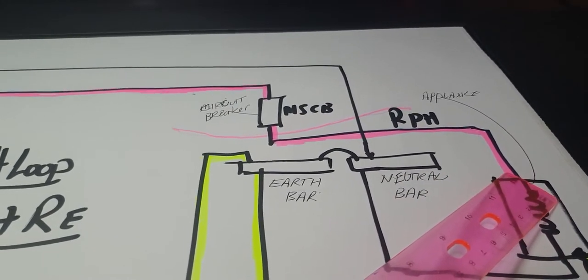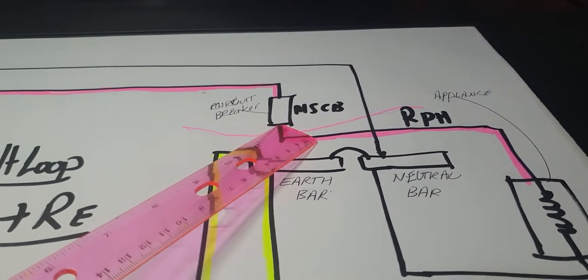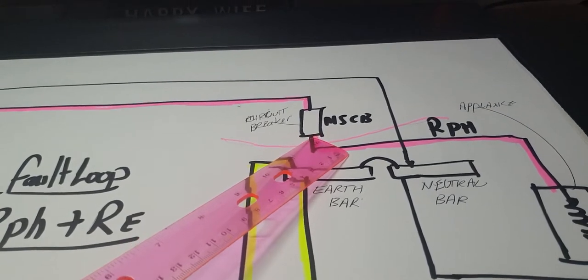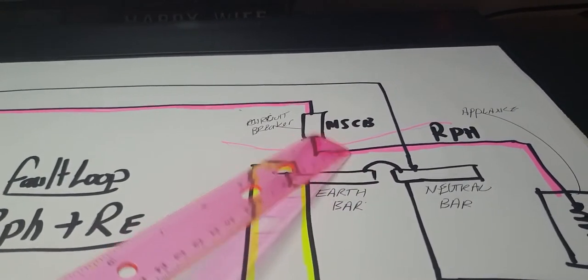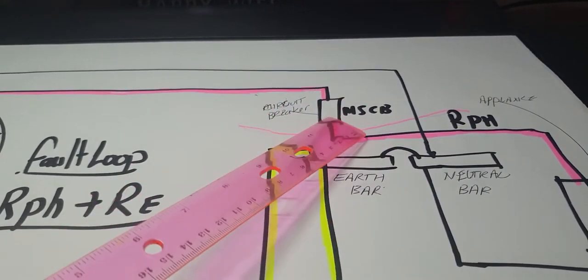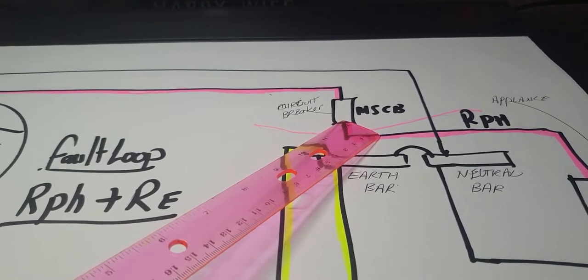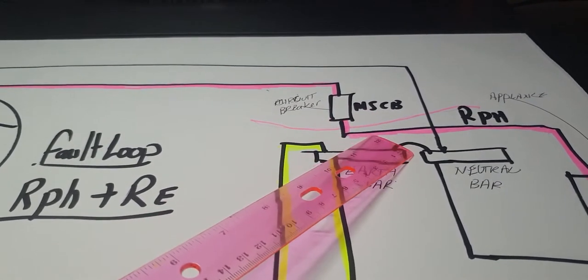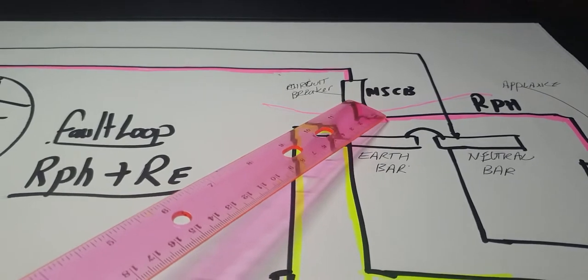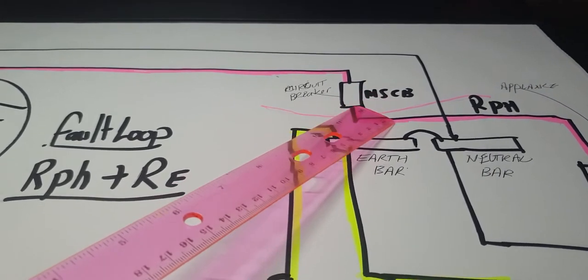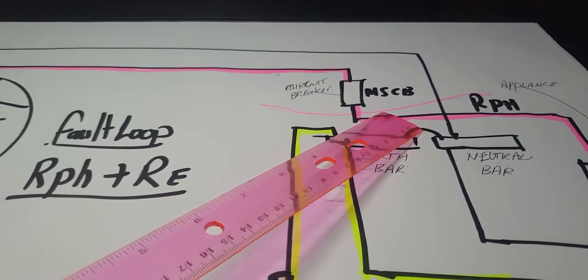If I have 2.5 mm wire, the maximum, depending if I'm running through thermal insulation, I can only run up to a 20 amp circuit breaker. The 3008 book covers us for all different sizes of how we rate our circuit breakers to protect the cable. With a fuse, we have HRC fuses with a 0.9 derating because of the thermal effect. If my cable can only take 20 amps, I have to derate it down by 2 amps, so 20 times 0.9, to allow for that 2 amps to heat up and trip the fuse wire.